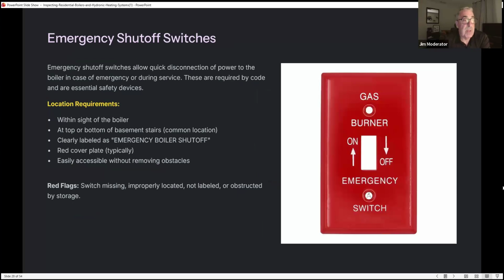Emergency shutoff switches. Emergency shutoff switches allow quick disconnect of power to the boiler in case of emergency or during service. These are required by code and are essential safety devices. Location requirements: within sight of the boiler, at the top or bottom of the basement stairs, clearly labeled as emergency shutoff boiler, red cover plate, typically easily accessible without removing obstacles. Red flags would be switches missing, improperly located, not labeled, or obstructed by storage.